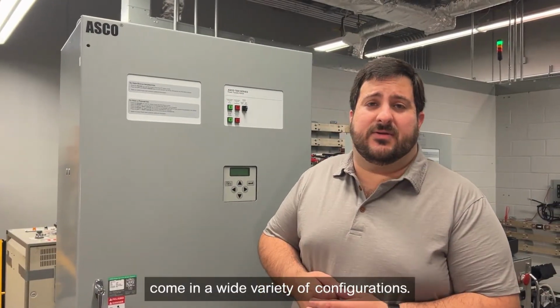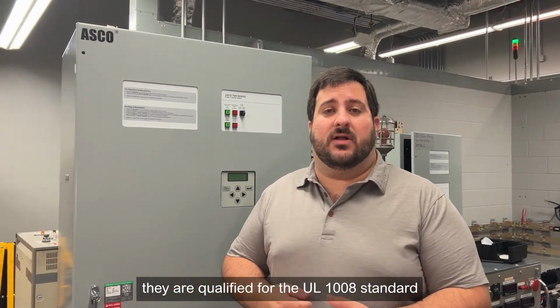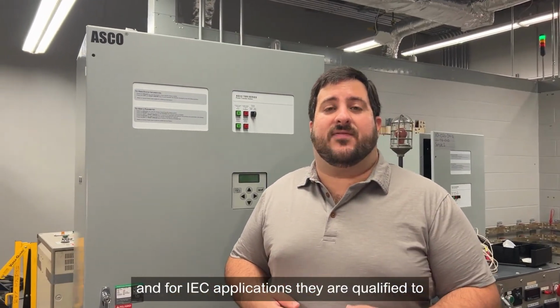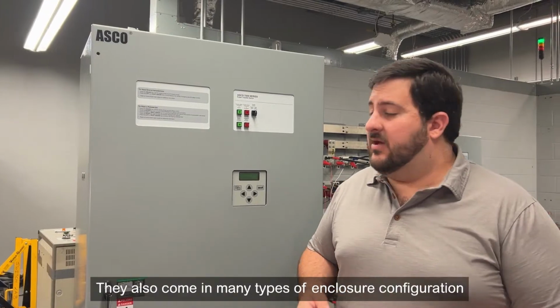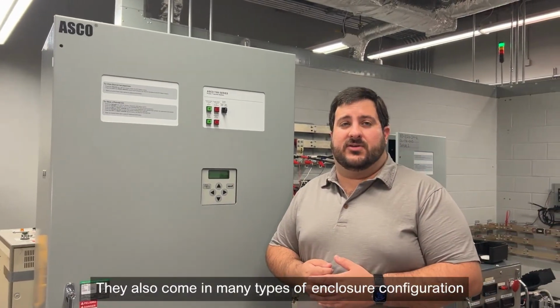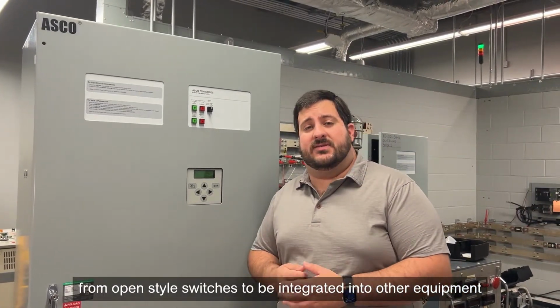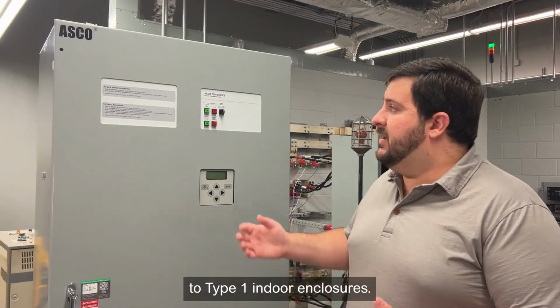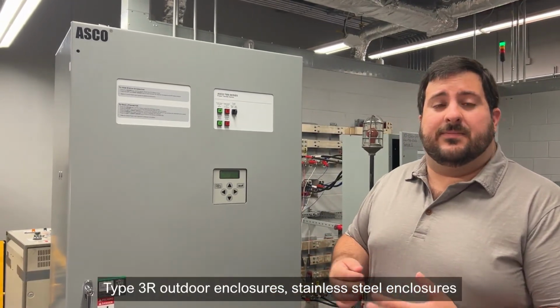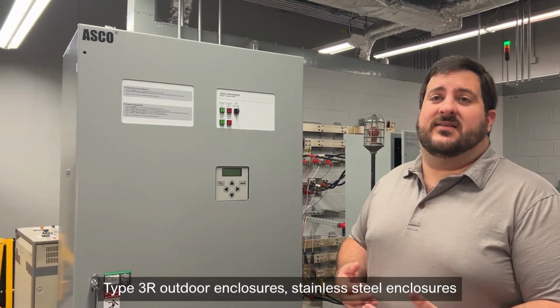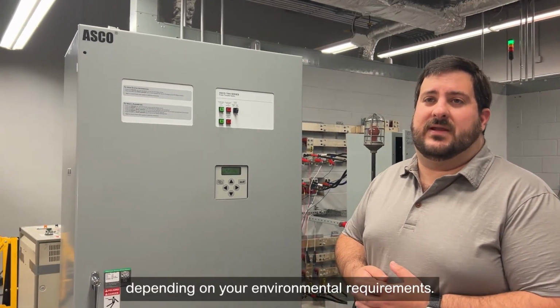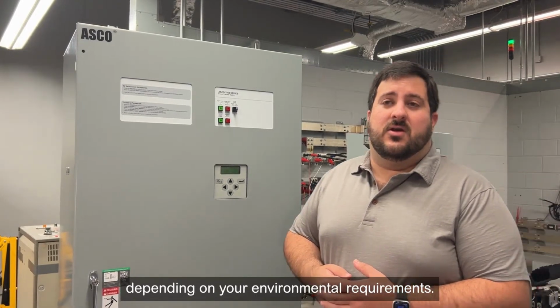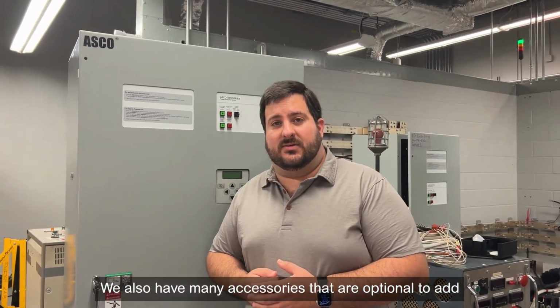Our transfer switches come in a wide variety of configurations. For NEMA applications, they are qualified to the UL 1008 standard. And for IEC applications, they are qualified to IEC 60947-6-1. They also come in many types of enclosure configurations, from open style switches to be integrated into other equipment, to type 1 indoor enclosures, type 3R outdoor enclosures, stainless steel enclosures, and many other options depending on your environmental requirements. We also have many accessories that are optional to add.